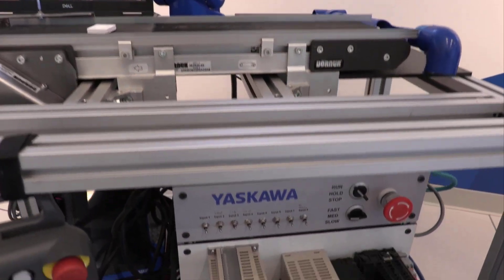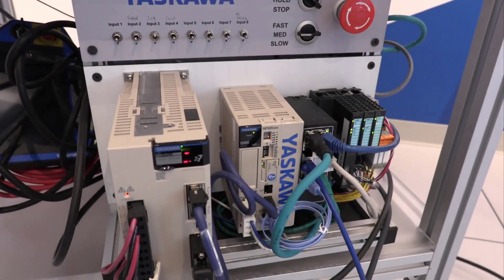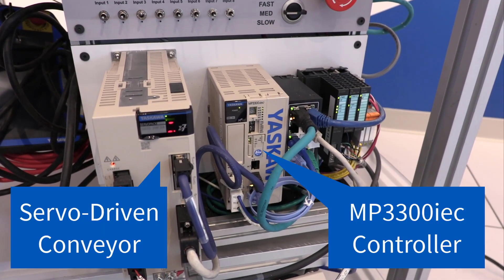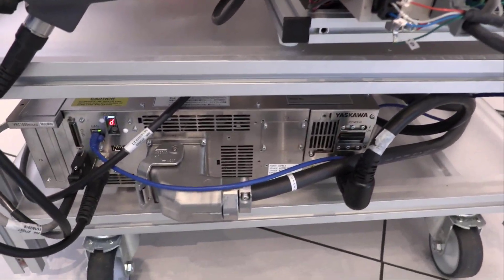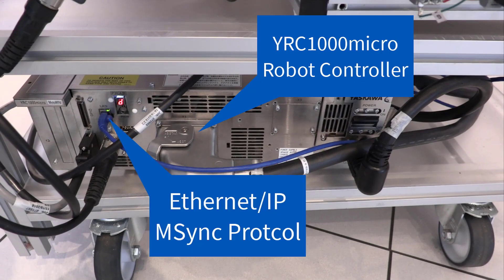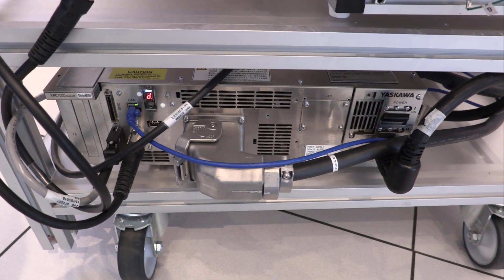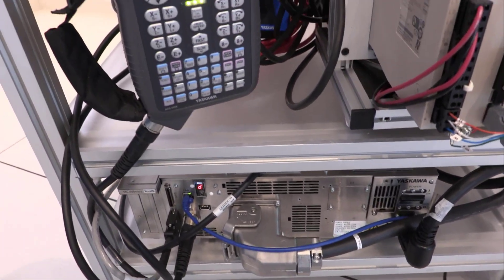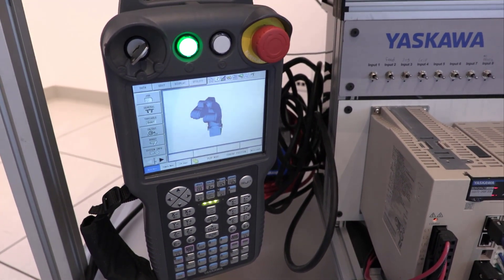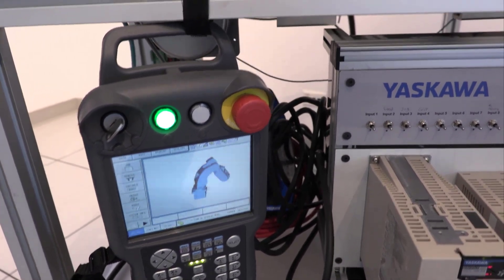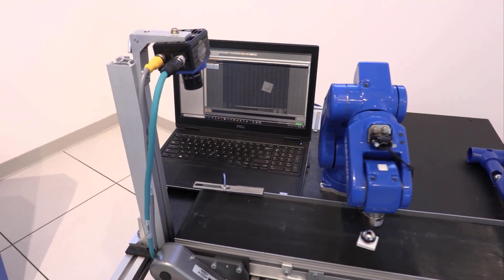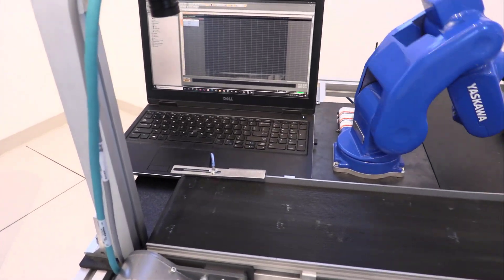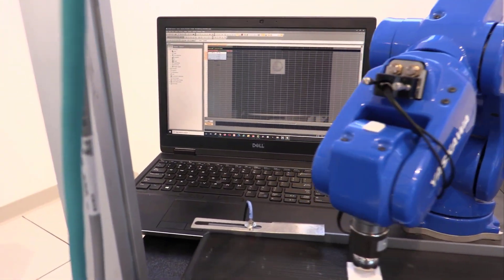Here also, the MPIEC controller uses the Mechatrolink 3 network to command the servo-driven conveyor. The MPIEC interfaces with the YRC1000 micro robot controller over Ethernet IP using the mSync protocol. The YRC1000 micro robot controller handles all the kinematics of the robot arm. The robot pendant shows a visualization of the motion. The vision system is triggered at regular intervals and reports the position of the tray to the MPIEC controller over Ethernet IP.